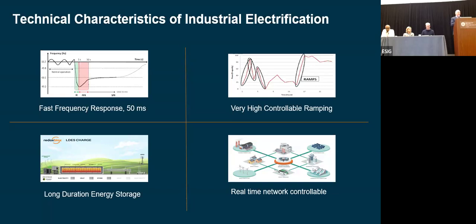You could have this running at, assuming you've got a 50 megawatt unit, set at 25. You can put it up to 50, down to 0, back up to 50 in under a second, and the load does not care—it's essentially just the amount of energy in getting transferred into heat, being stored, and delivered out as heat when needed. You can do very long duration energy storage because the capital costs are relatively low. If you think about the 3-week example, if a lot of your demand is more controllable, it's energy storage rather than electricity storage.